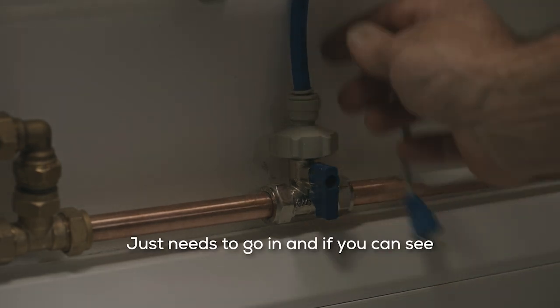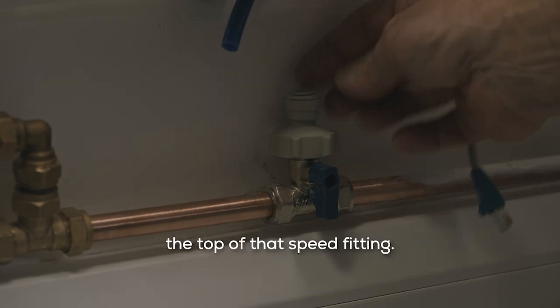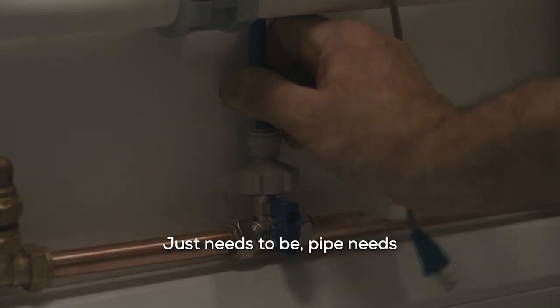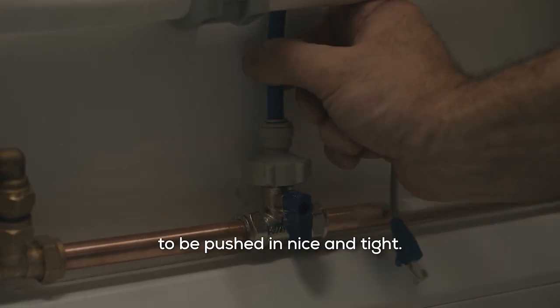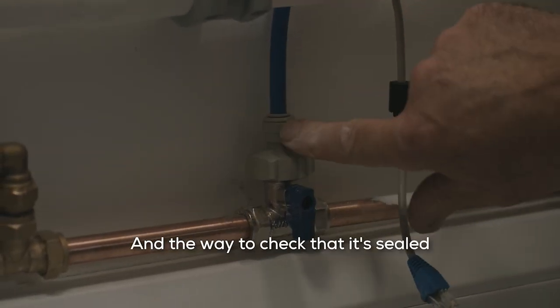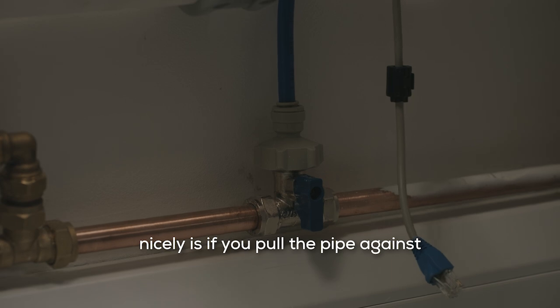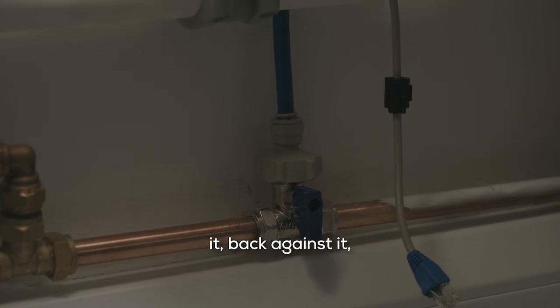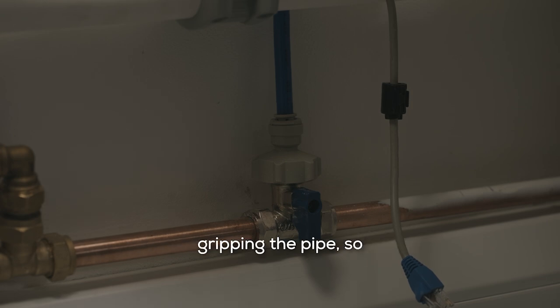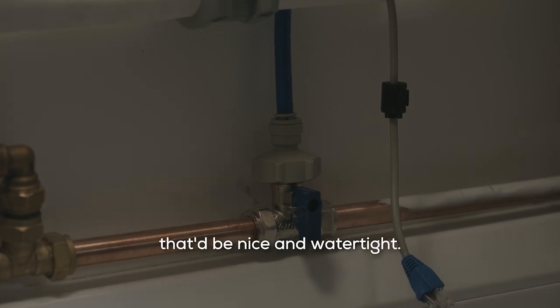Just needs to go in, and if you can see, there's a little collar on the top of that speed fitting. The pipe needs to be pushed in nice and tight. And the way to check that it's sealed nicely is if you pull the pipe back against it, you'll see that the collar lifts up. That collar lifting up means that it's gripping the pipe, so that'll be nice and watertight.